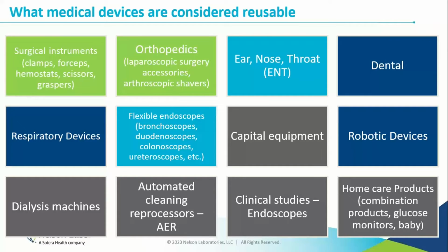And yes, in 2021, it was pretty clear in the standard that that is what they want. Robotic devices, that's an industry that's growing exponentially and very fast. We're seeing more and more robotic devices come through, but they come with their own challenges for validations and simulated use cycles that we have to follow. They have their own challenges on how we're supposed to challenge these devices as well. So depending on the criticality of the product, the validation changes as well.